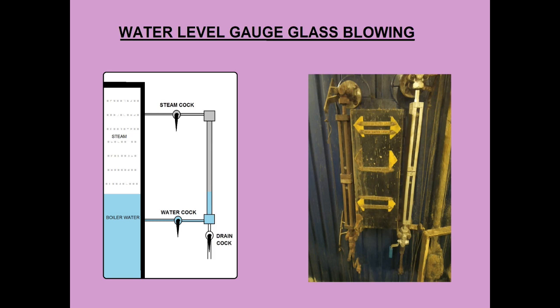First open the water cock. The water must rise up to the top of the glass gradually. This is because the steam trapped on top of the glass gets condensed, and due to the formation of a vacuum, water rises to the top. Then open the steam cock; now the water in the glass must fall to the level of the water in the boiler.